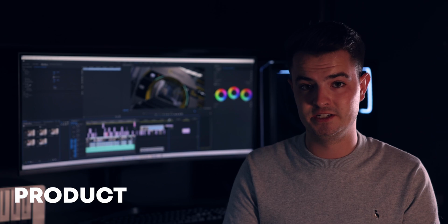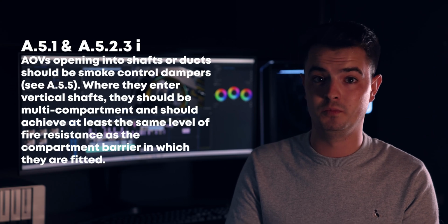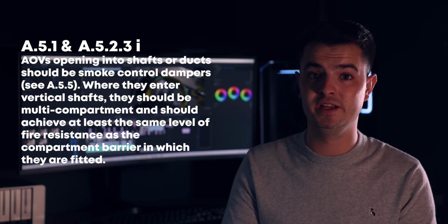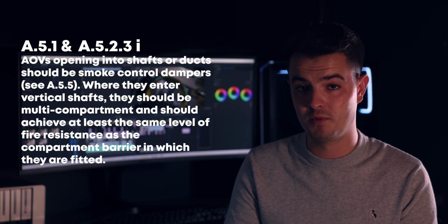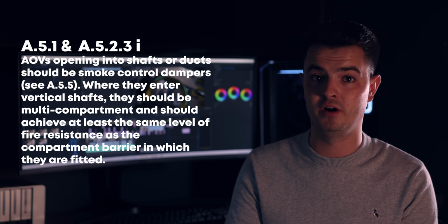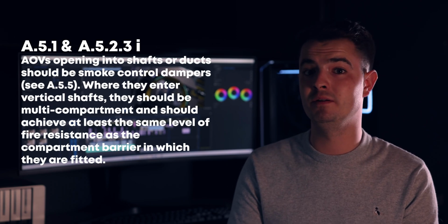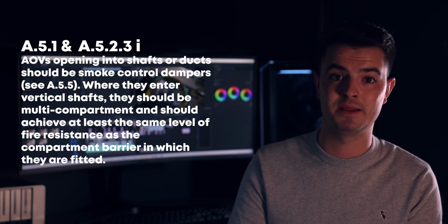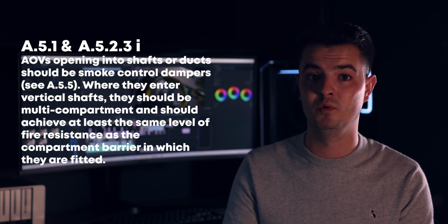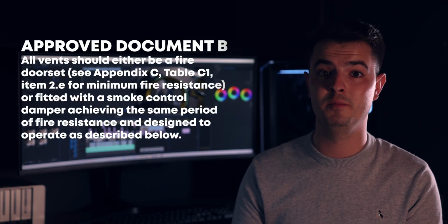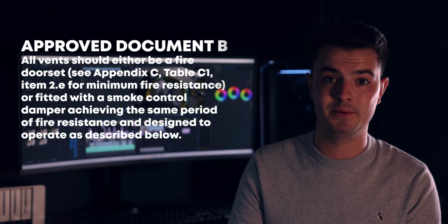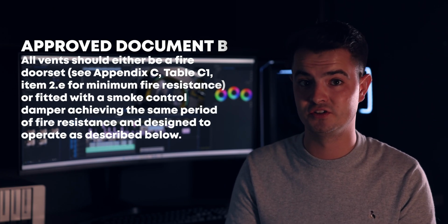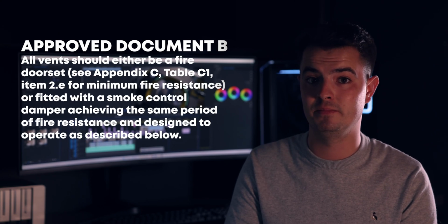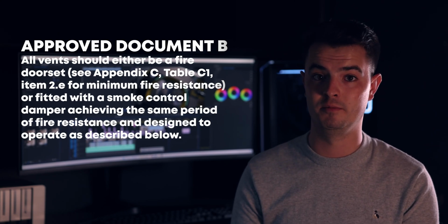Moving on to product-related changes, the most major change is A.5.1 and A.5.2.3i, which states AOVs opening into the shafts or ducts should be smoke control dampers, see A.5.5. Where they enter vertical shafts, they should be multi-compartment and should achieve at least the same level of fire resistance as the compartment barrier in which they are fitted. This is a significant departure from Approved Document B, which states all vents should either be a fire door set, see Appendix C, Table C1, Item 2E for minimum fire resistance, or fitted with a smoke control damper achieving the same period of fire resistance and designed to operate as described below.